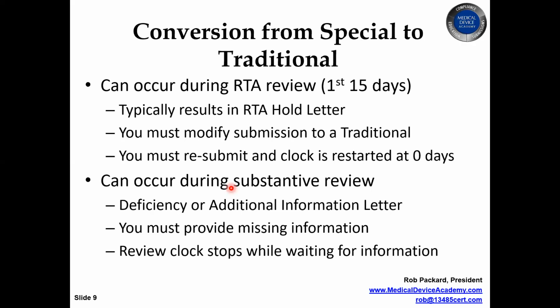If they don't make that decision right away and they wait until after 15 days to say, this really belongs as a traditional submission, then they're going to give you the deficiency list as a request for additional information, and the clock stops, but it doesn't go back to 0. So when you get an RTA hold letter, you restart your clock and you resubmit.